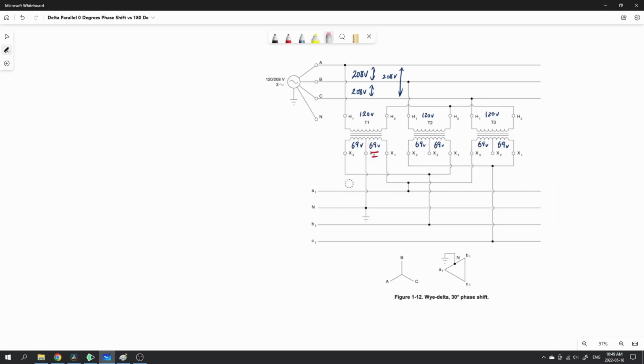Okay, let's go between B and neutral now. So B bus coming up here, and we got to get to the neutral there, so we'll take the shortest path. Looks like we're coming over here, going through this winding between X2 and X3 on transformer number 1, and getting to that neutral there. So that's where we're picking up the 69 volts as well. Okay, it looks good. So A and B are obviously 69 volts because we're only going through one of the windings there, going from either A or B to this neutral bus now.